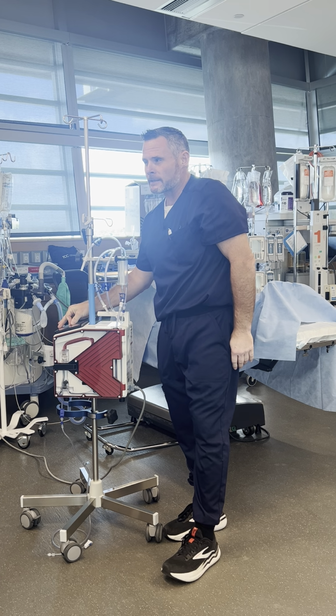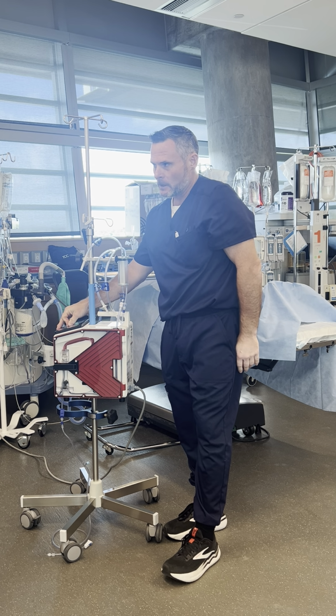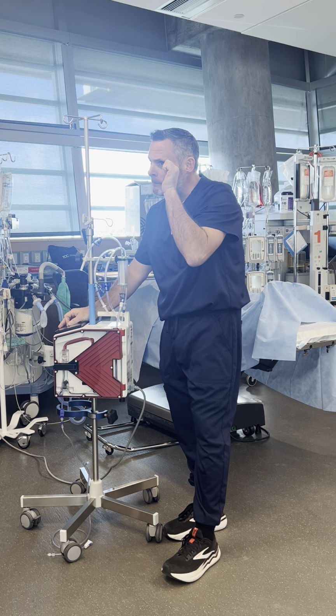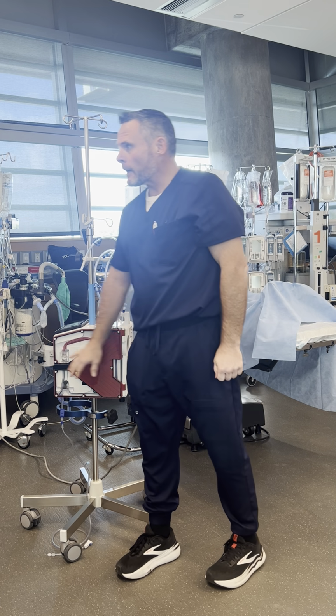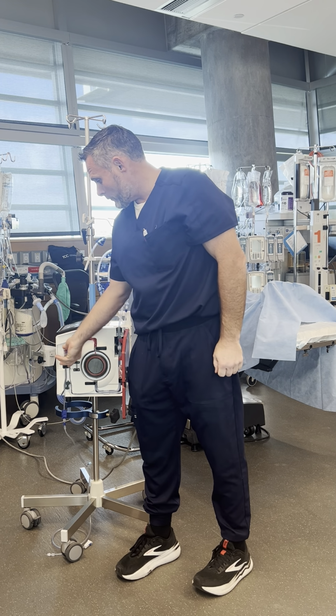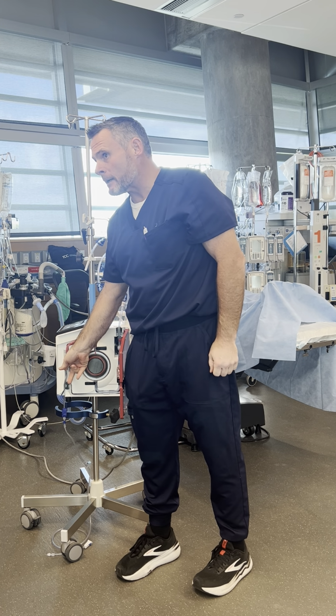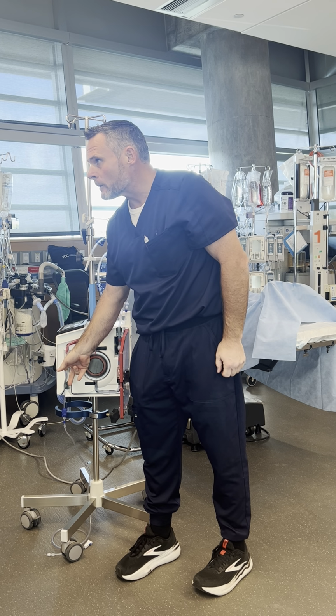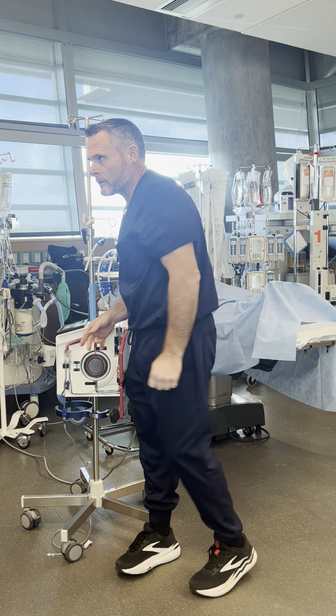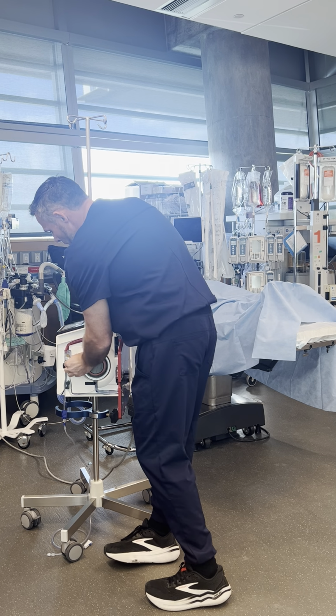The guy who made this device taught me this shortcut and it works every time. Air detection squeeze - pump, pump, pump, pump, pump. Okay, and the cause of that is somebody getting an angry finger or it's a dirty sensor. You want to keep that clean with alcohol only. Hear that? Alcohol only, no purple wipes on this thing. Air detection squeeze, pump, pump, pump.